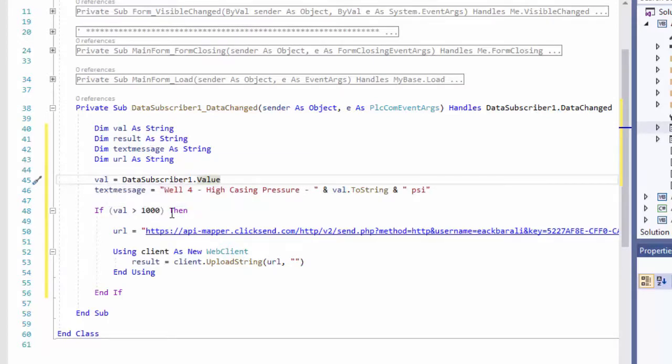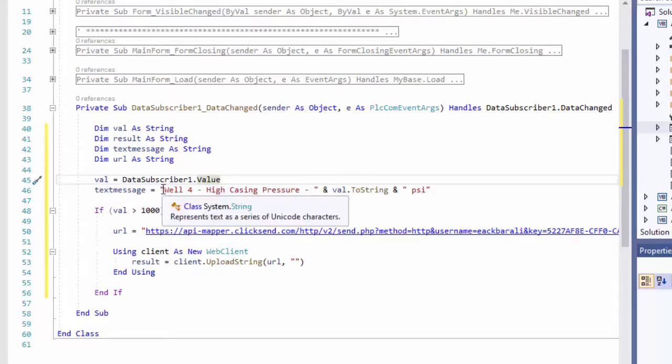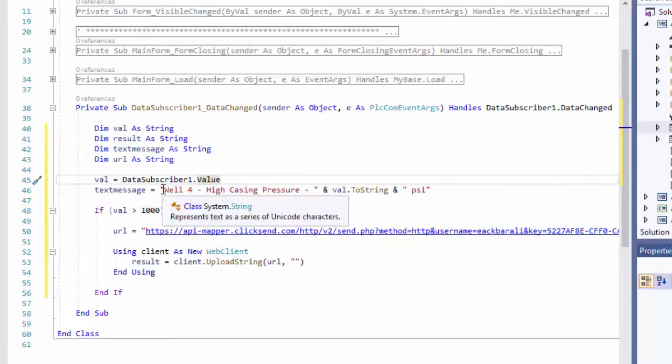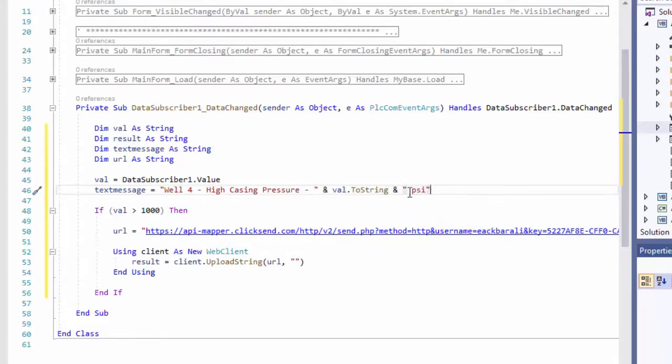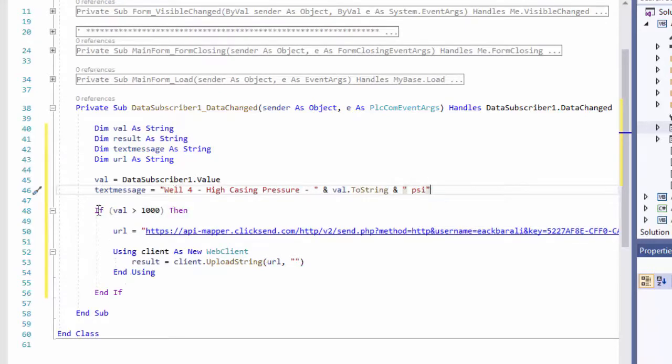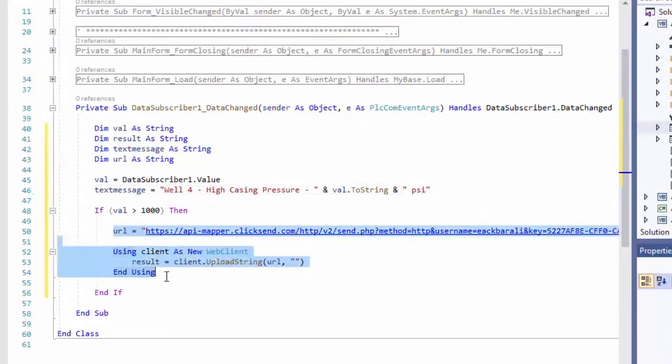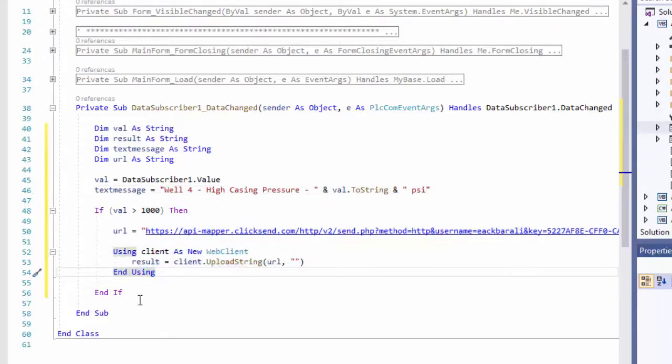If the value getting from the holding register is greater than 1000, we need to send an alarm message. I'm saying, 'Well number 4 high casing pressure' and val.ToString puts the value of the high casing pressure in PSI. So that's our text message to be sent.